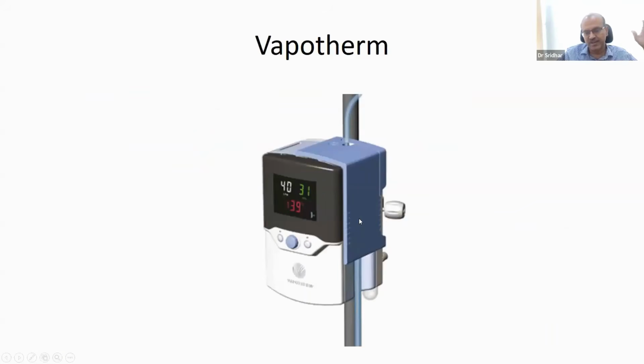So this is a Vapotherm device. I don't know if any of you use it. So it's quite simple. The water vapor cartridge is inside here, and the blender is built in. And obviously the gas flow is connected, same as you connect the ventilator, air and oxygen connections. It gives alarms when the appropriate level is not met.